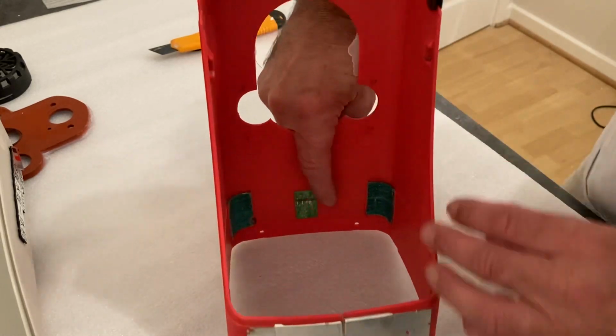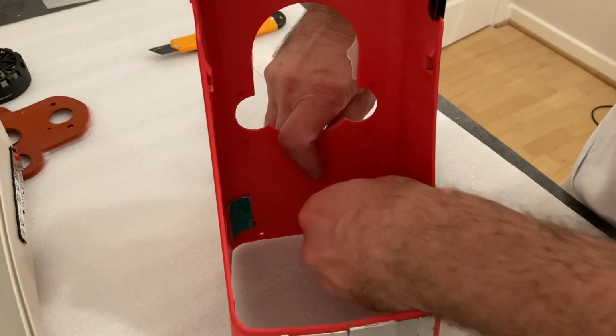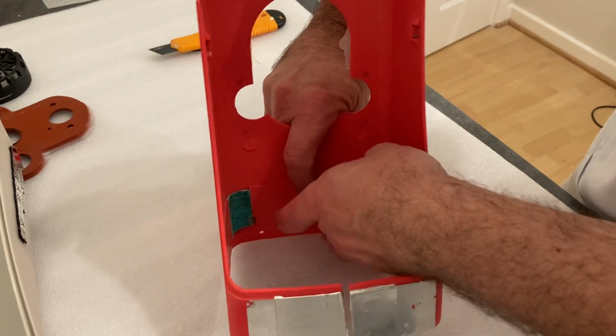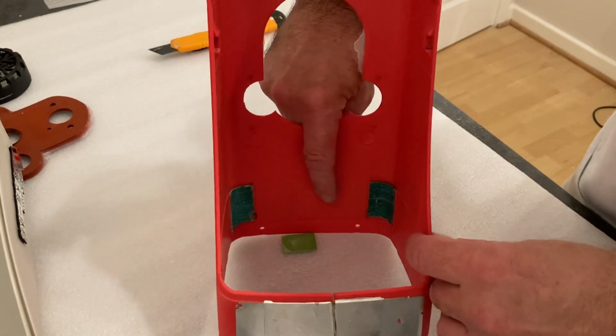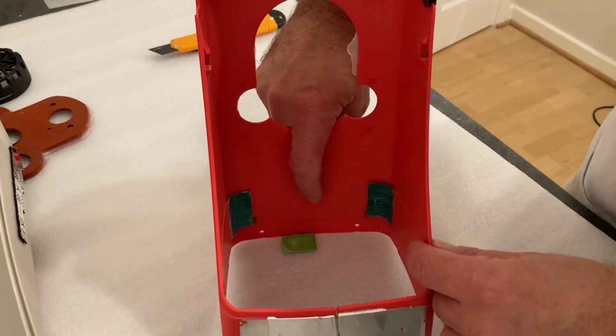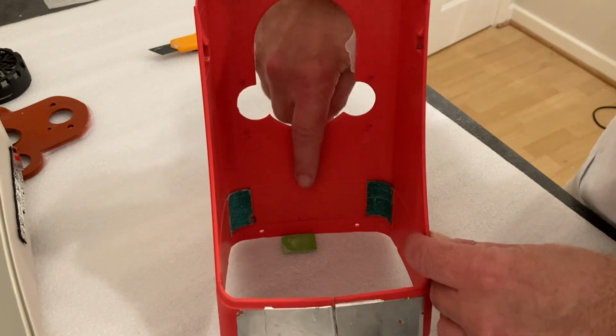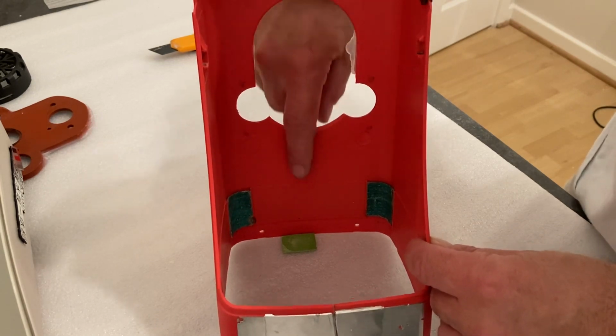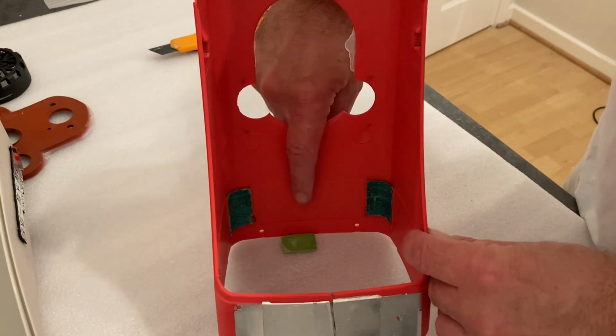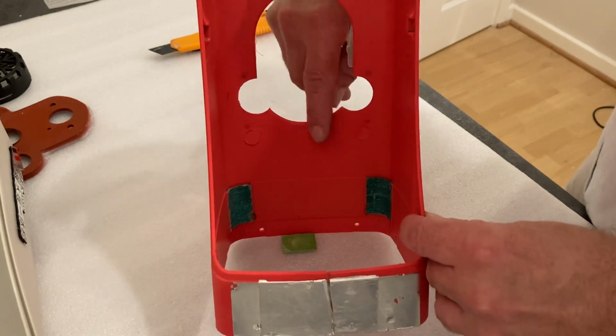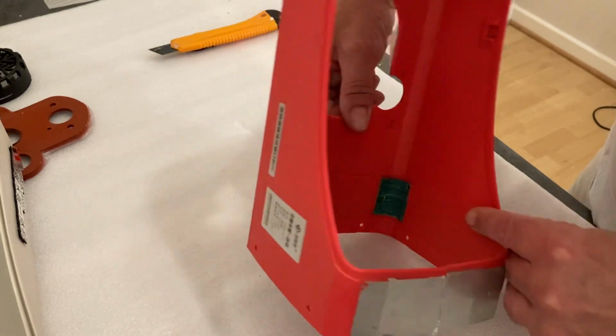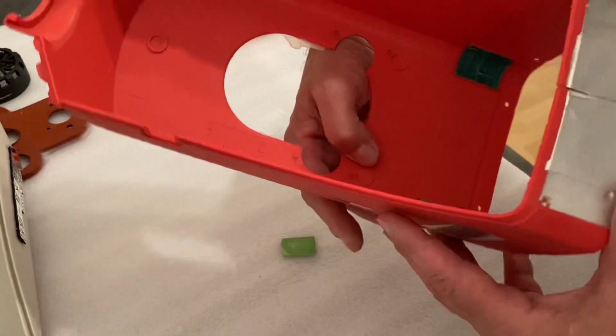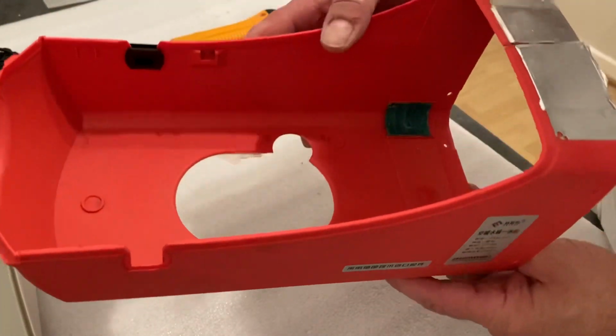That's where the heat exchanger sits - no, man, that's not good, that needs sticking back. That's where the heat exchanger sits, and there's no airflow under there whatsoever. I'm talking about the water heat exchanger - there's no airflow under there. That is permanently touching, but there's no scarring whatsoever, and I can't see any soot or any burning anywhere in there.